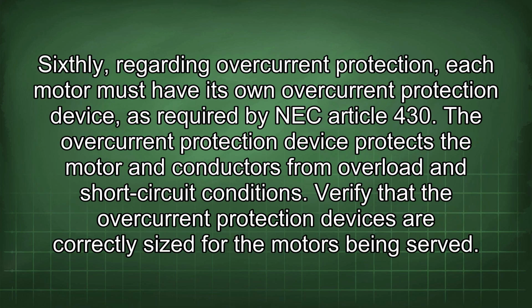Sixthly, regarding overcurrent protection, each motor must have its own overcurrent protection device, as required by NEC Article 430. The overcurrent protection device protects the motor and conductors from overload and short-circuit conditions. Verify that the overcurrent protection devices are correctly sized for the motors being served.